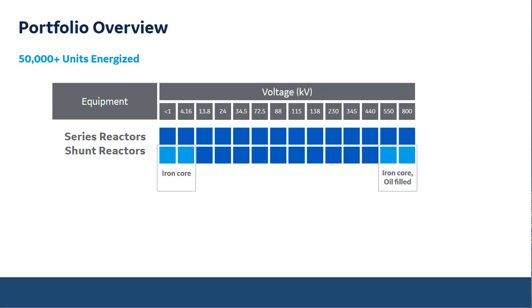And why am I saying that? A shunt reactor is connected at the full potential of the line. So if you have a 230 kV line, you have that shunt reactor connected to the full phase to ground voltage of that 230 kV line. So the voltage stress on a shunt reactor is much higher than on a series reactor. So that's why we divide it into two families. You'll probably notice that series reactors are wider and shorter, and shunt reactors are thinner and taller. The reason for that is the voltage stress and insulation requirements that shunt reactors require and series reactors do not.